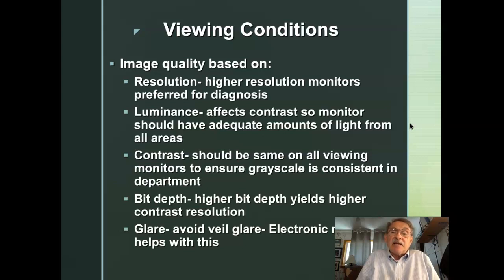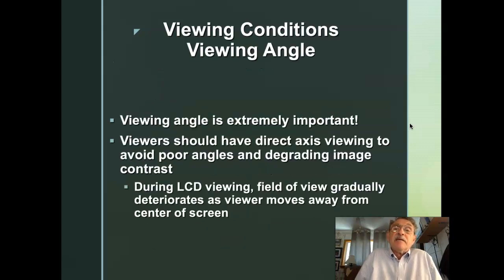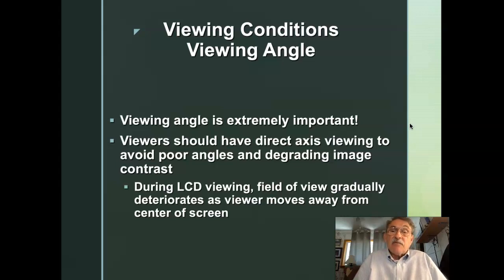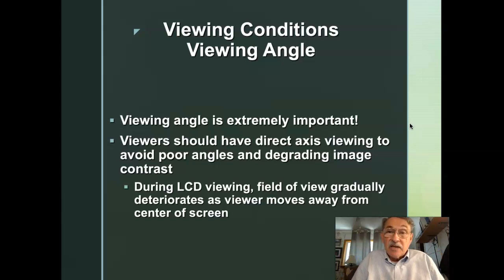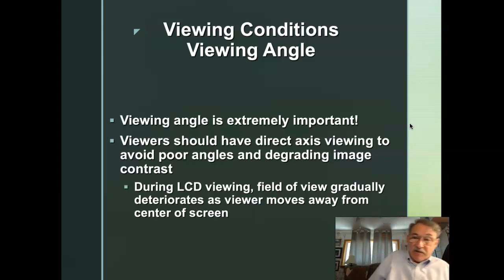Higher bit depth yields higher contrast resolution — more gray shades available. Avoiding veil glare: electronic masking helps eliminate veil glare. Viewing angle is important — viewers and physicians should have direct-axis viewing to avoid poor angles and degraded image contrast. During LCD viewing, the field of view gradually deteriorates as the viewer moves away from the center of the screen. Best case is for the physician to view the screen perpendicularly, which gives the best viewing conditions. Viewing from the side detracts from the image.